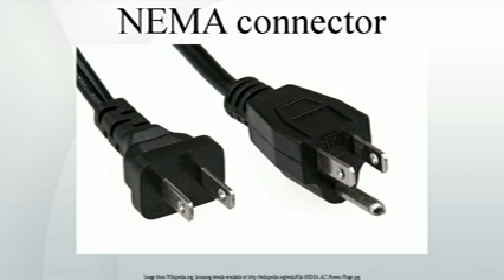NEMA L22. NEMA L22 connectors are used with circuits with a maximum specified voltage of 277/480 VAC. Supply connections are intended for 3-phase, 5-wire LLNG circuits with a nominal supply voltage of 460 VLL and 265 VLN.